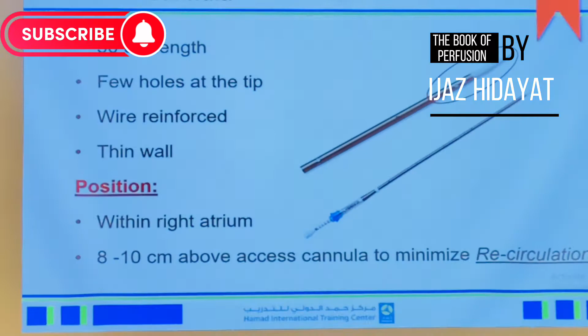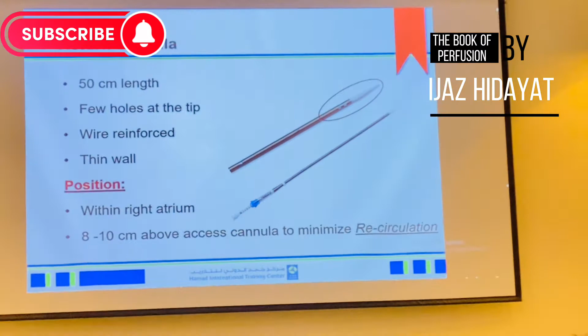This one is your return cannula. The return cannula goes very far, I think up to 50 centimeters in length, with a few holes. This cannula is not multi-hole. It has holes only at the tip, because we don't want multiple holes, otherwise there is a chance of recirculation. The position of this cannula is within the right atrium. The difference between the positions of your access and return is around 8 to 10 centimeters. If it is less than 8 to 10 centimeters, there is a chance of recirculation.